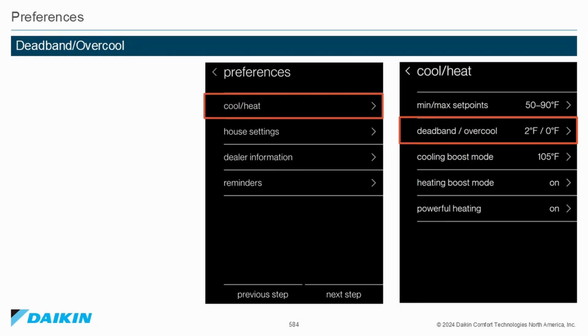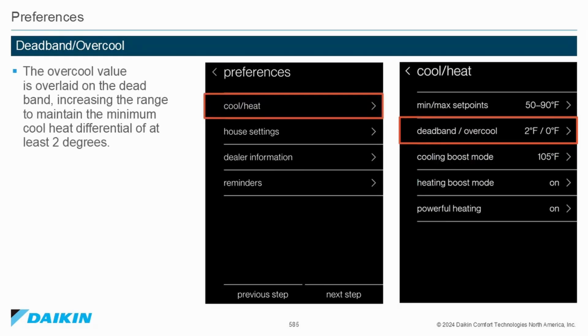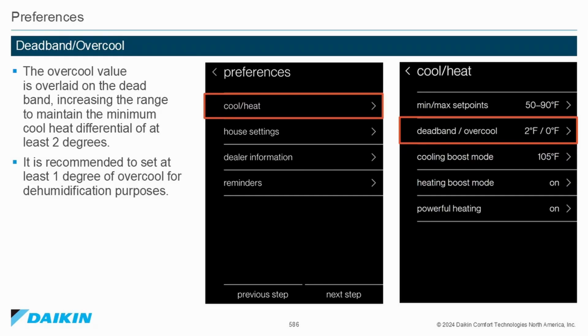Preferences. Deadband overcool. The overcool value is overlaid on the deadband, increasing the range to maintain the minimum cool heat differential of at least 2 degrees. It is recommended to set at least 1 degree of overcool for dehumidification purposes.